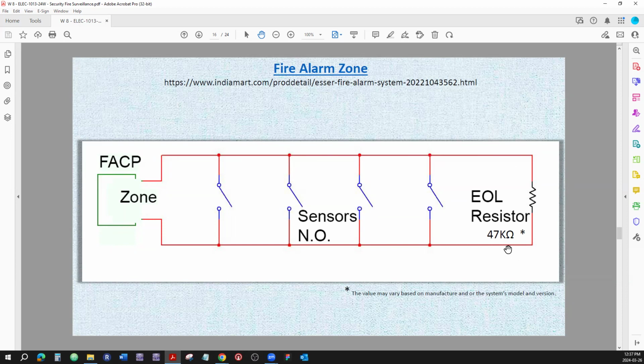There are two conditions that might happen. A line could get broken somewhere - lines do get broken, it's a wire, somebody could be doing work and cut your wire by mistake, or something can happen. Then the system doesn't see the 47 kilo ohms or the resistor at the end. Is it going to trigger an alarm? No, it's going to trigger what's called a trouble condition. When in trouble condition, the panel produces periodic annoying beeps, and people in the office notice those beeps and look for where the noise is coming from - oh, it's from the fire alarm. They wonder if they're in trouble, but it says 'in case of trouble, call this number' right there. So they call, and it's usually just a service visit that's needed.